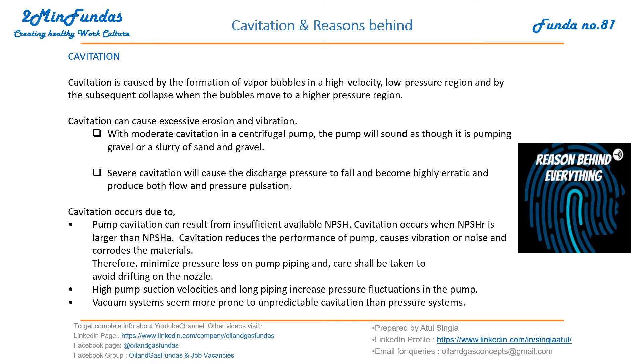Now let us discuss why cavitation occurs. Pump cavitation can result from insufficient available NPSH. If insufficient NPSH is available, it will cause pump cavitation. Cavitation occurs when the required NPSH is larger than the available NPSH — whatever is required is more than available, then cavitation will occur.